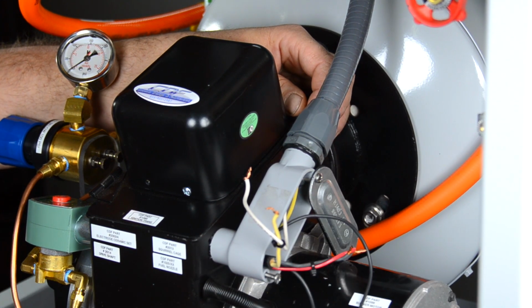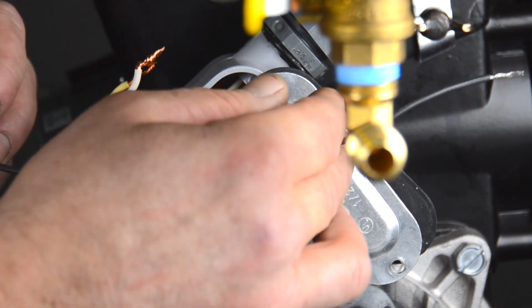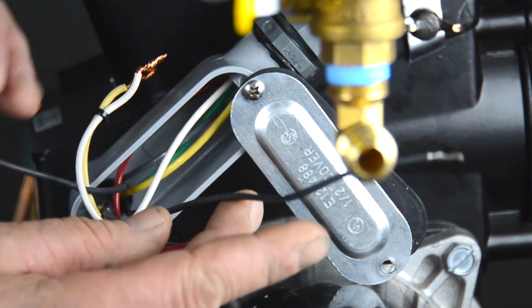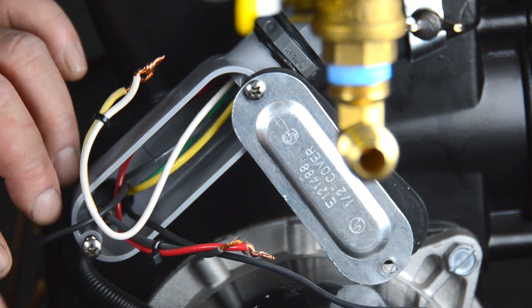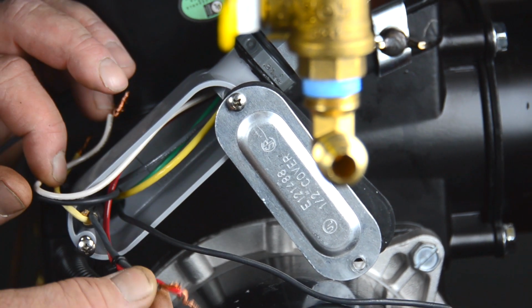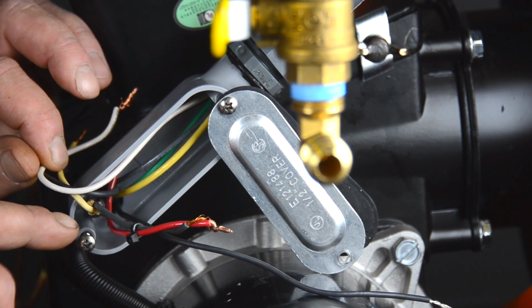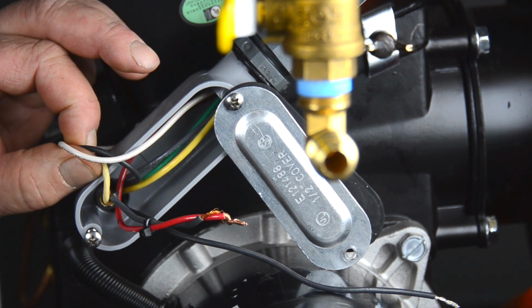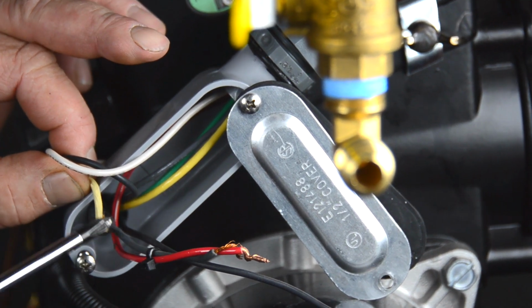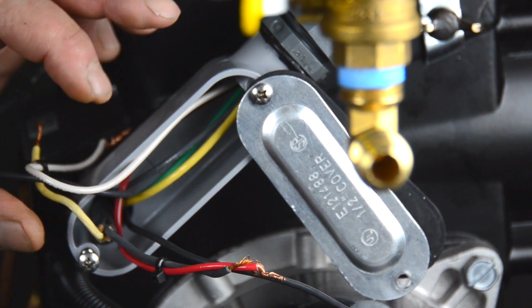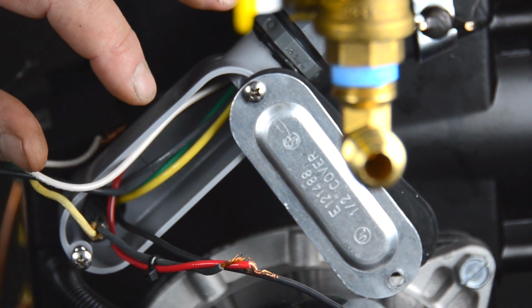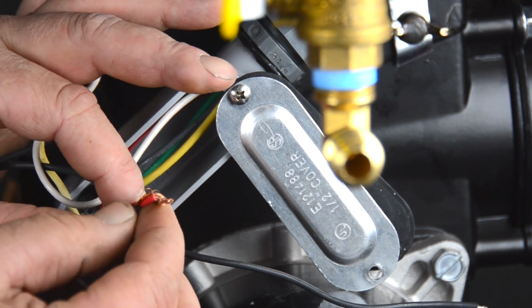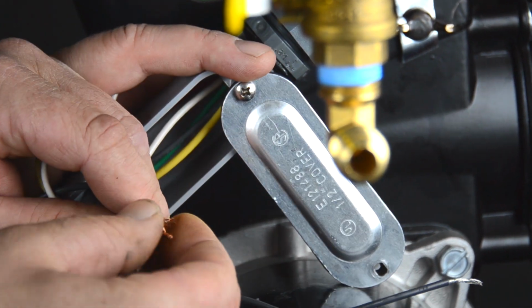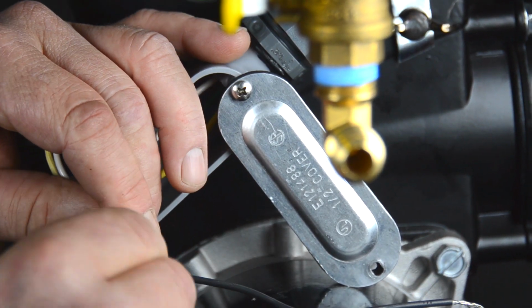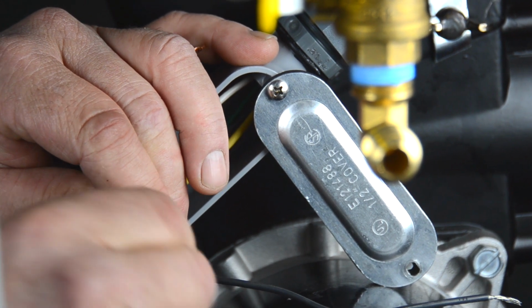And next we'll make the connections to hook the transformer back up. Alright, now here are your two transformer wires coming out and back into your LB box. You'll note at this time you got a black wire from the motor. That's the cord that has the jacket on in here. Here, these are your motor wires. And you hook the one red wire that comes down the conduit. So you got a black motor wire, your red power wire. Make sure they're together.